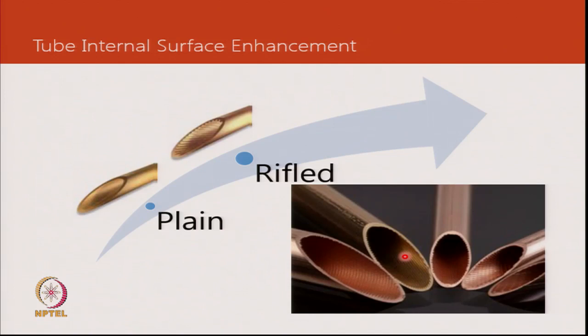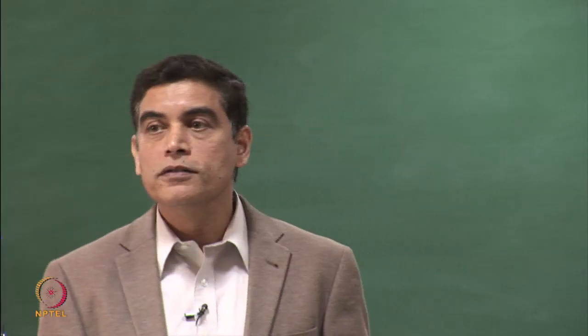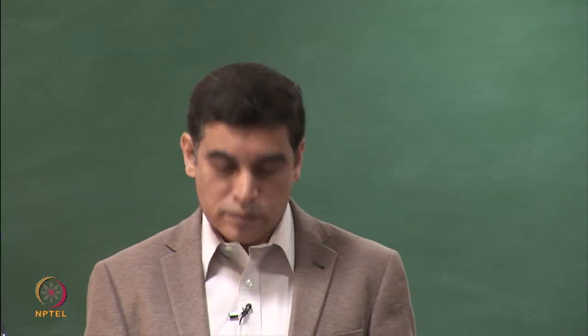So as manufacturing processes for drawing copper tube have evolved, it has been possible to make some more complex shapes inside the copper tube and get higher refrigerant heat transfer coefficients. The key thing that we must remember is that this becomes necessary only after you have taken the air side coefficient substantially high, because otherwise the air side heat transfer coefficient is the constraint in the amount of heat that we will transfer.